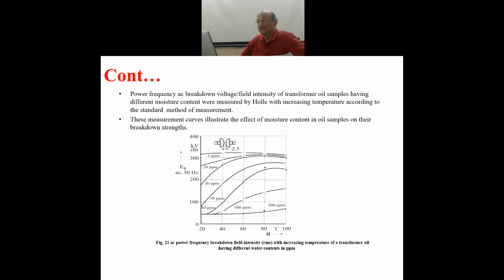So you have to always define under what conditions you have measured the breakdown strength of oil samples. And it is very difficult to measure extremely high values, as I mentioned, for highly purified oil, because that requires a lot of effort. That is why the concept of practical breakdown strength has been developed.